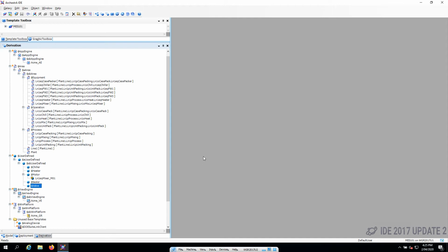Now this has two valves, so we're going to Control-N, VO1, new, VO2. You can see why I'm doing this, to give them unique prefixes. This way System Platform doesn't complain about their lack of uniqueness. When it comes to their contained names later on when we drop them in the hierarchy, we'll simplify them to V1, V2 so that the name of the tag isn't so long. You'll see that process in just a moment.